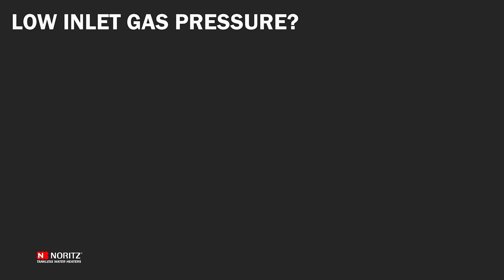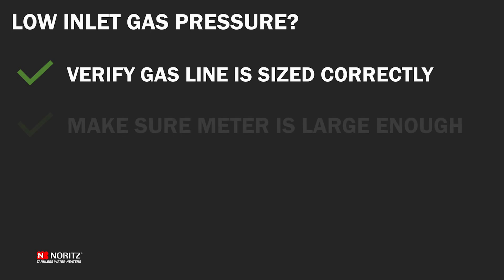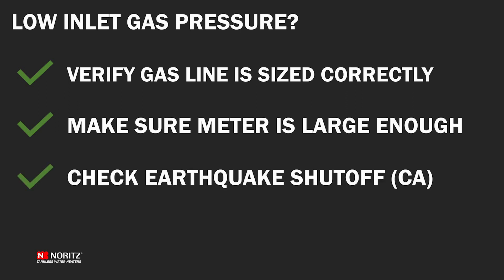If either the static or dynamic inlet gas pressure is below the minimum requirements of the unit, verify the gas line size and length are appropriate according to the guidelines in the installation manual. Also, make sure the gas meter or gas regulator is large enough to handle the total BTU load of all gas appliances at the home. Additionally, for California installations, check that the earthquake safety shutoff has not been tripped.